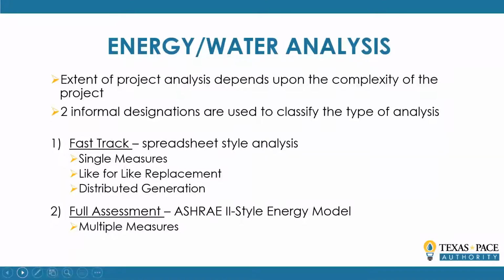So the extent of the analysis really depends on the nature of the project, how deep we go. We've come up with two informal designations to characterize these approaches, outlined in our guidelines. One is what we call a fast track approach - this is almost like a desk spreadsheet type analysis for single measures. This would be something like replacing HVAC with the same type, size, and tonnage, just looking at common run hours plus efficiency rating of the old versus new equipment - so like-to-like replacement. Could be the same for lighting, which can also be done in a very simple way.